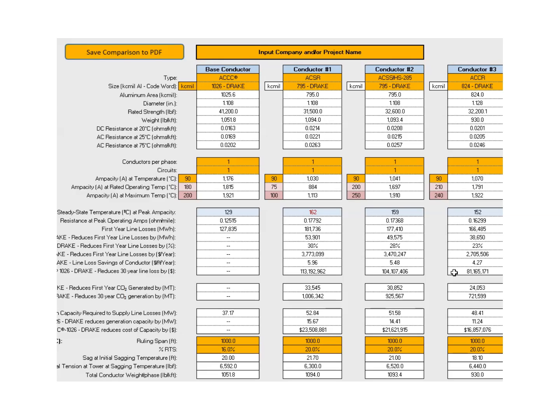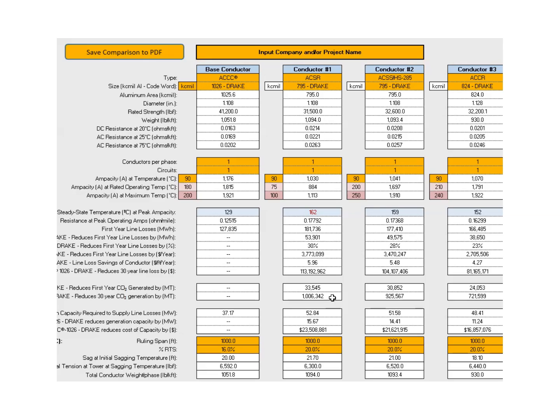Again, with these assumptions and a Drake-sized conductor. Also, we're doing a significant job of reducing emissions. Assuming that we use a US average of 1.372 pounds of CO2 per kilowatt hour, we'd be saving over 33,000 metric tons of CO2 every year, or about a million metric tons of CO2 over the life of a 30-year service life of the conductor at that point in time.